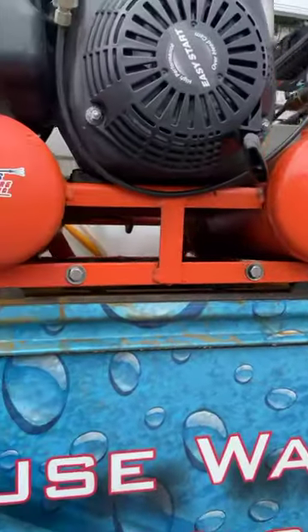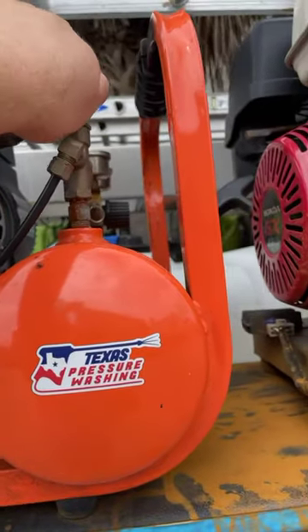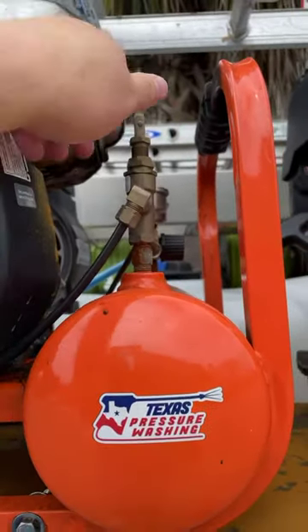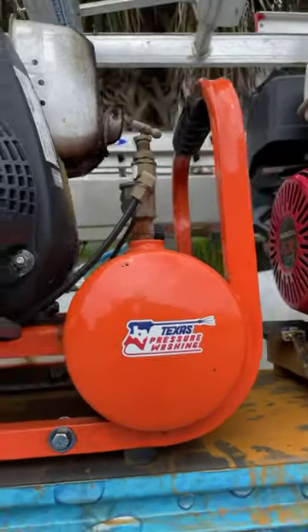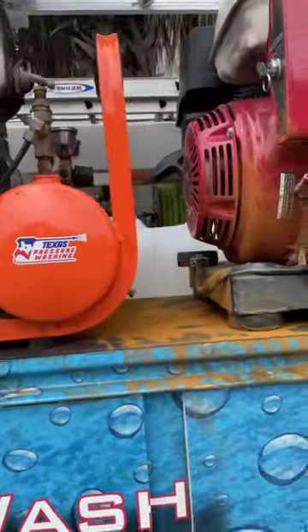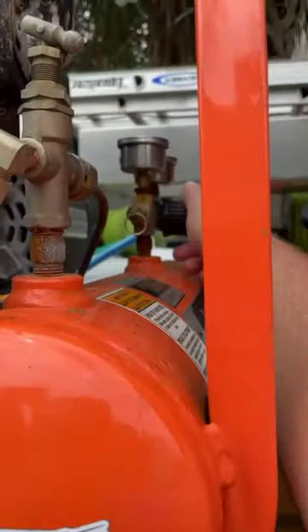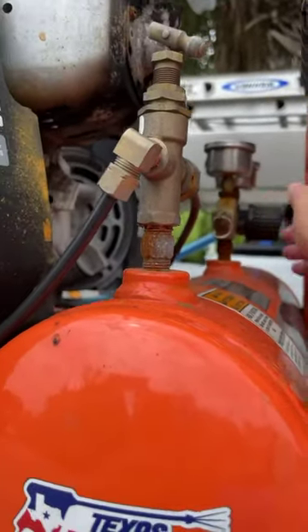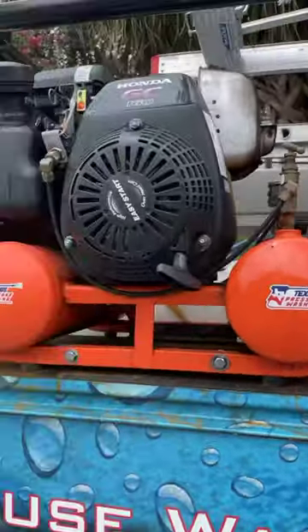The compressor has been great, no issues. One thing I will tell guys who have issues: you've got to put this in bypass mode when you start it, or it won't let the diaphragm reset. I had a guy who was just killing himself trying to figure it out, and that was the issue — he wasn't putting it in bypass. After you put it in bypass, you let it build up to 155, and then you crank this down until it reaches 100. We use a stepladder so we can see what's going on.